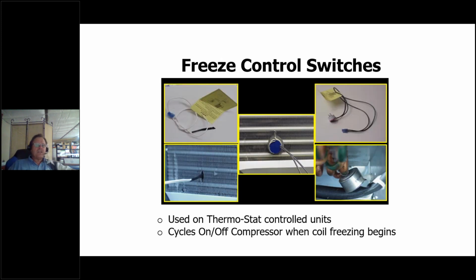Now, there's another device called a freeze control switch. This is on the evaporator coils. Each one of these pictures shows a different type of freeze control switch. What had happened was the manufacturers kept having all these people turning these air conditioners in for warranty that they had burned up the compressor. And so they got to looking, and what had happened is that these people were running these air conditioners on low fan speed, and maybe they weren't cleaning their filters, so they were actually restricting the airflow across the coils.